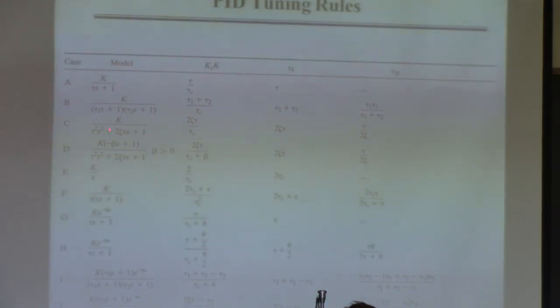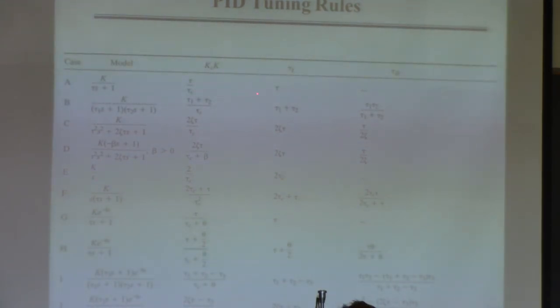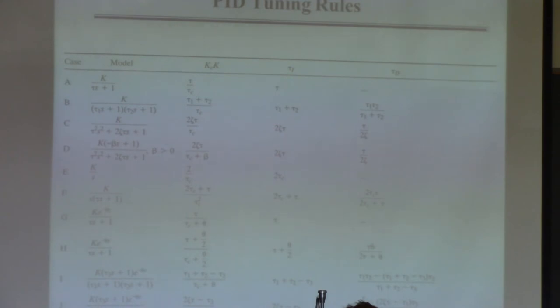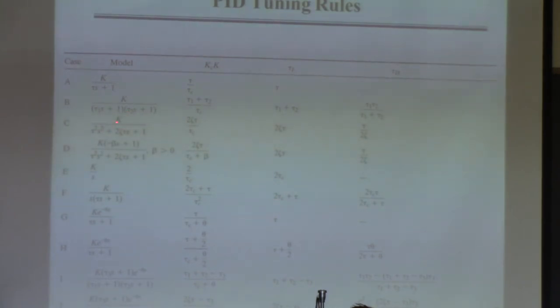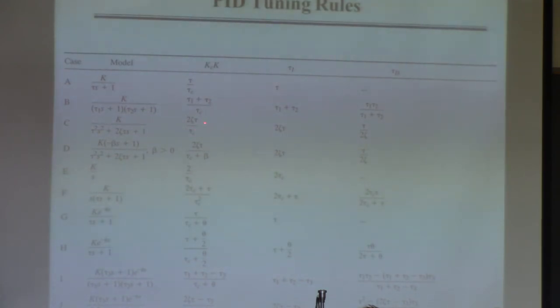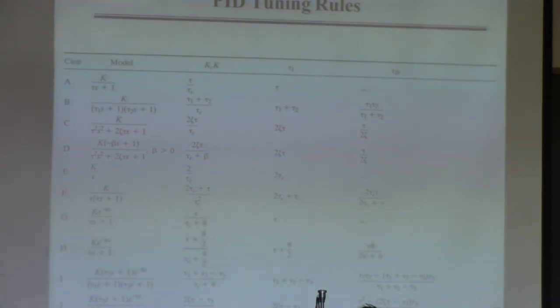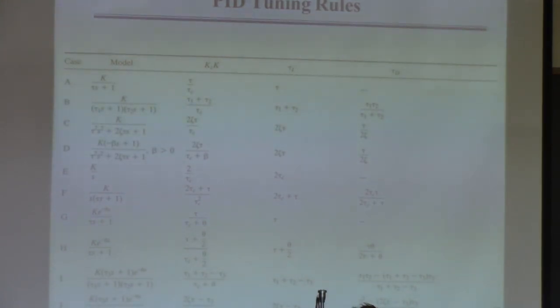This provides another way to tune a PID controller. You go in the table, find the entry that corresponds to your particular case — in some cases it's PI, in others it's PID. This is actually my preferred way of tuning any PID controller. To use these formulas you need the process parameters, and then you have to choose tau_C — like one half tau, something like that.